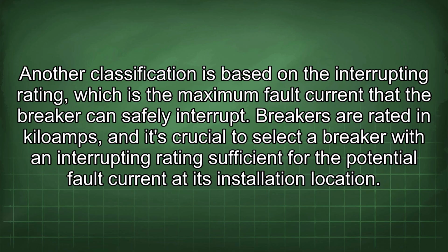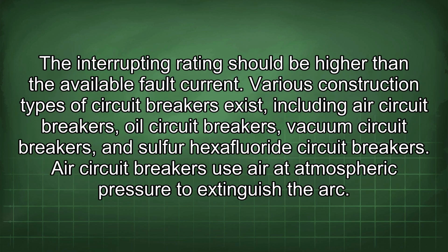Another classification is based on the interrupting rating, which is the maximum fault current that the breaker can safely interrupt. Breakers are rated in kiloamps, and it's crucial to select a breaker with an interrupting rating sufficient for the potential fault current at its installation location. The interrupting rating should be higher than the available fault current.